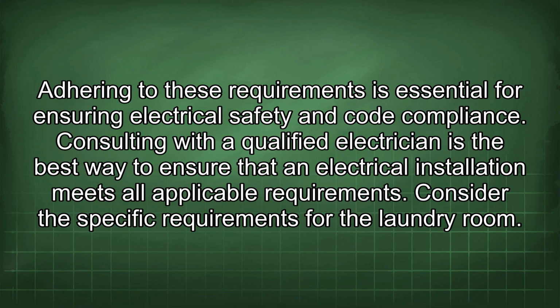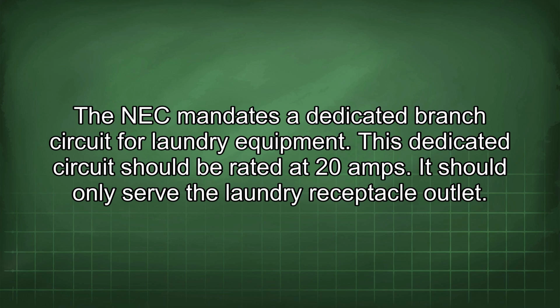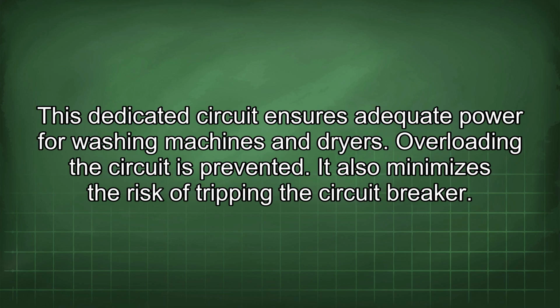Consider the specific requirements for the laundry room. The NEC mandates a dedicated branch circuit for laundry equipment. This dedicated circuit should be rated at 20 amps. It should only serve the laundry receptacle outlet. This dedicated circuit ensures adequate power for washing machines and dryers. Overloading the circuit is prevented. It also minimizes the risk of tripping the circuit breaker.